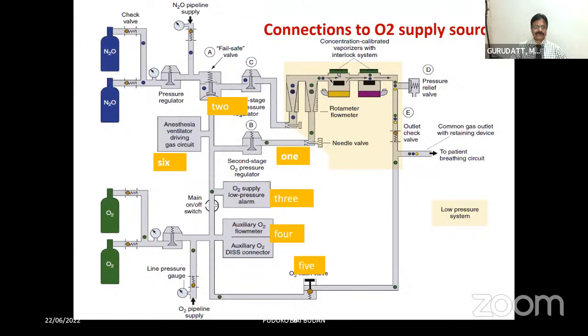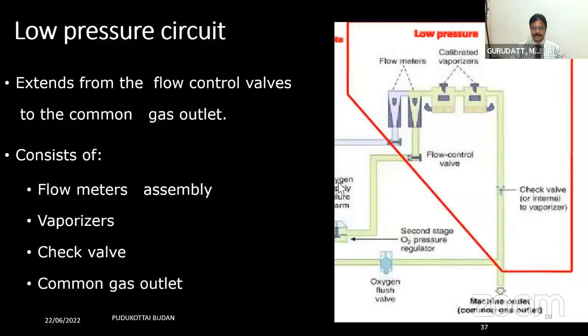Because in GE machines, the ventilator we have is a bellows ventilator. It is a double circuit ventilator wherein you require a driving gas also. So the oxygen is used as a driving gas for driving the fresh gases that are collected in the bellows in GE machines. This 6th connection is not there in Draeger, because in Draeger we have a piston driven ventilator. We don't have a bellows ventilator. So you can always say there are 6 connections for the oxygen supply source.